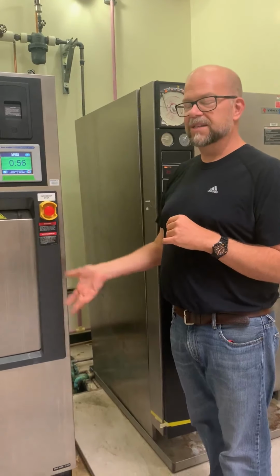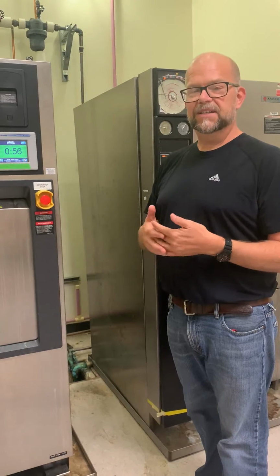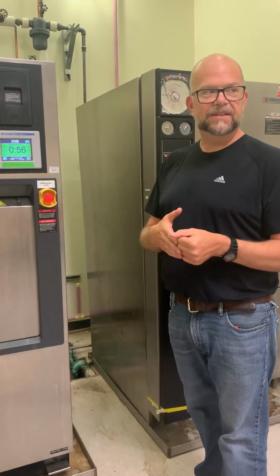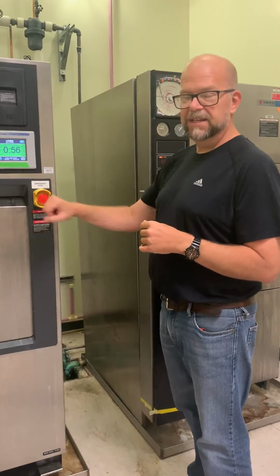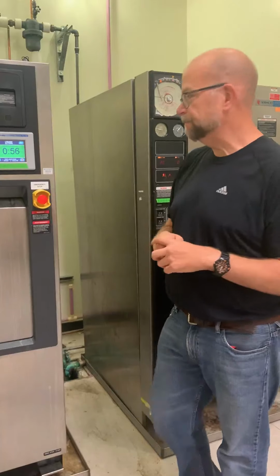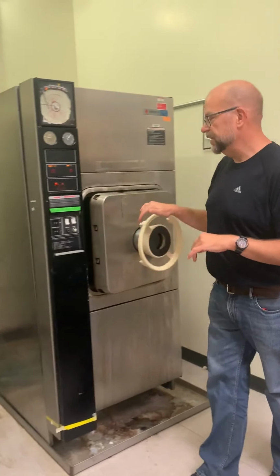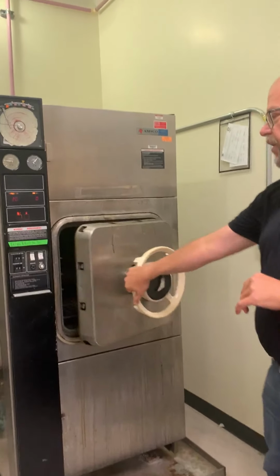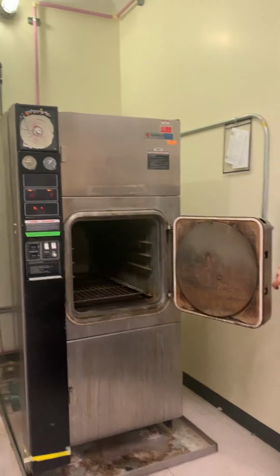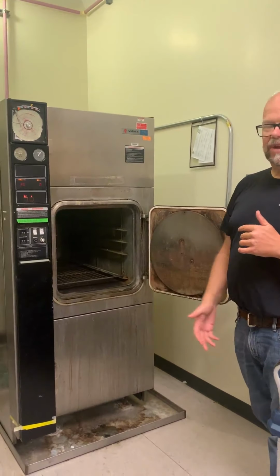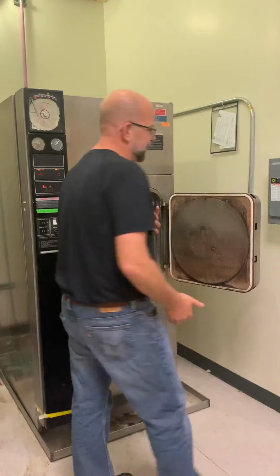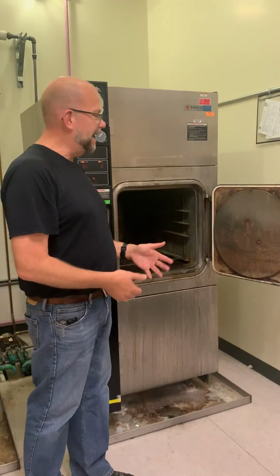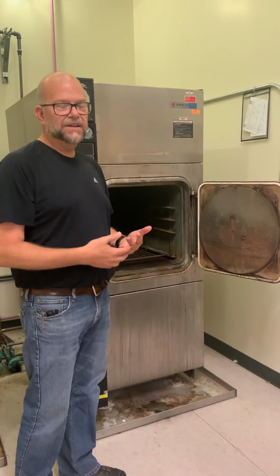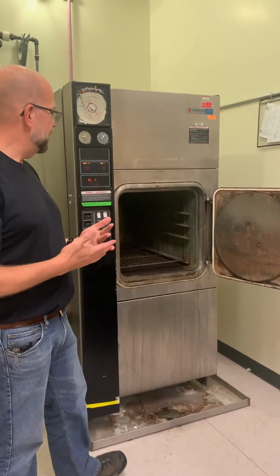It will cause this machine to recycle, and it's going to tie it up for an hour doing nothing. So only use this in case of emergency. The second machine is a bit older. It's a hatch style door. So when we're opening this door, we're pulling stuff in or out of this autoclave. It's a good idea to do it from this side. Don't have your back up against there so you bump into it, you burn yourself.